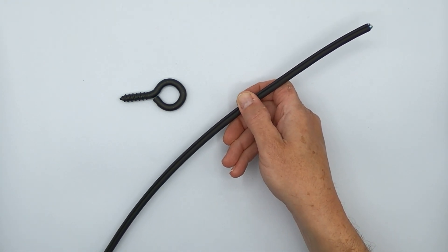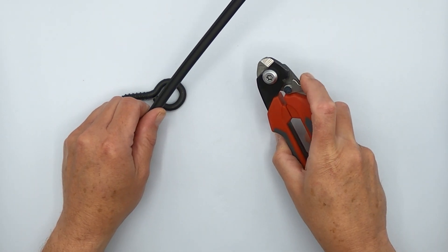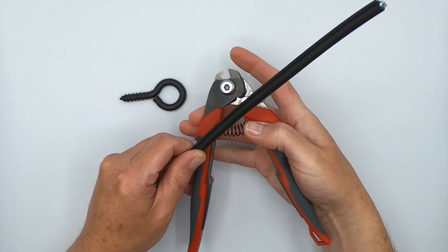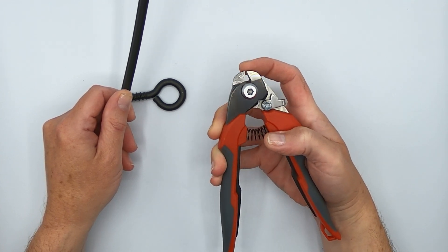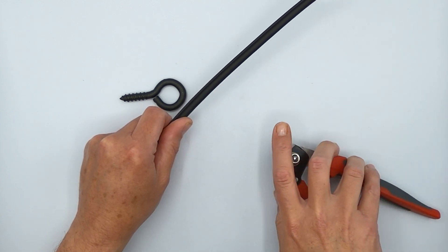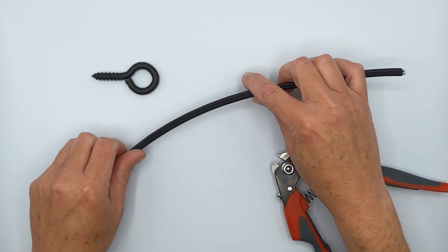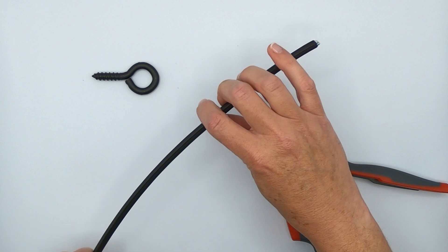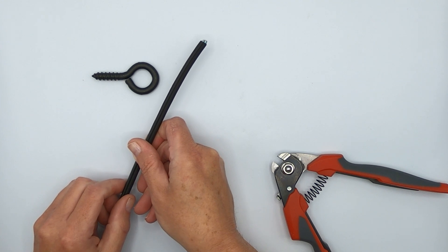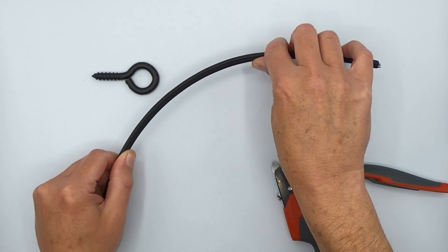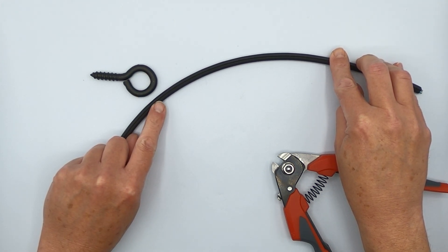So there is a way to strip this back without damaging your cable and to snip it without damaging your cable. The first thing is snipping. And so what you use for that is a high strength steel rope cutter like one of these. It's a specialty cutter. You can get them at Home Depot, Lowe's, wherever. And it's very high strength, high leverage, and it's sharp and it's designed to get through strong wire like this. So what you do is you've got your eye hook already mounted on one side and on the other. You've already got your hardware up. And the next step is your cable is coming up to the eye hook because you drug it up there with you on the ladder, right? And then the cable is going to continue going on.